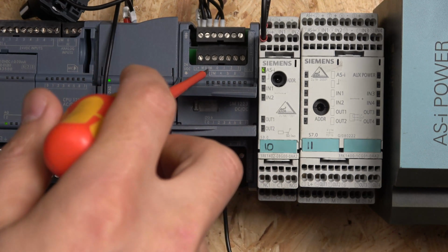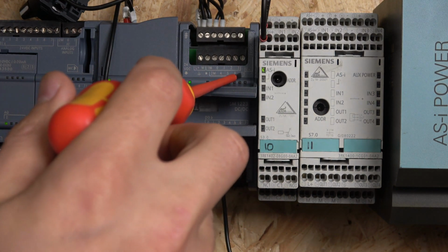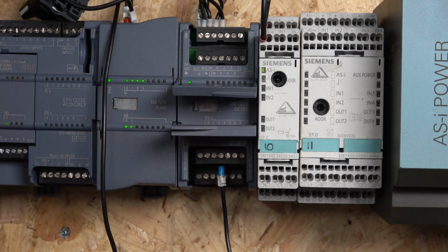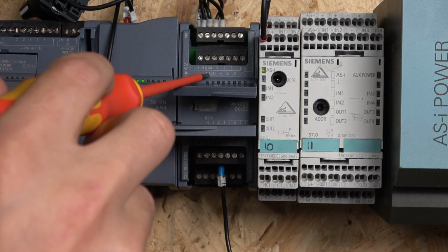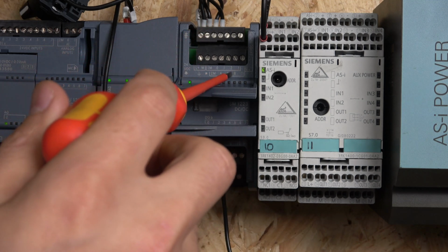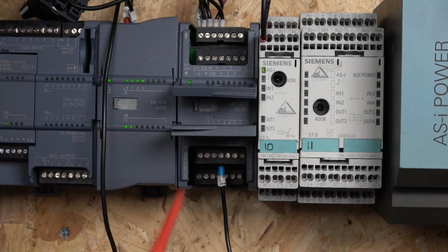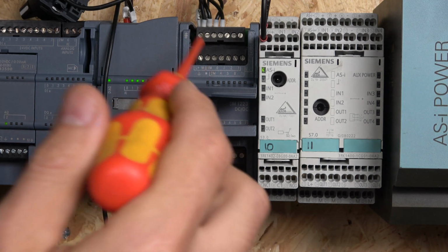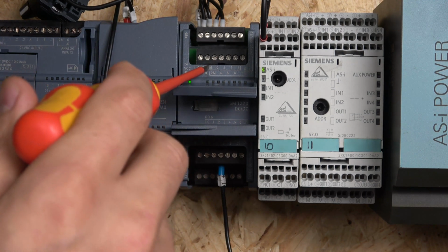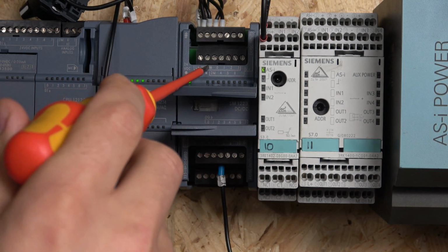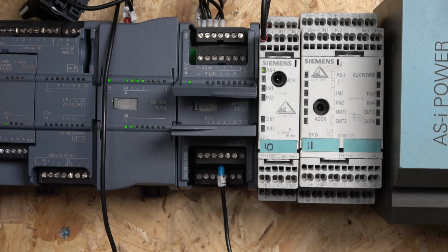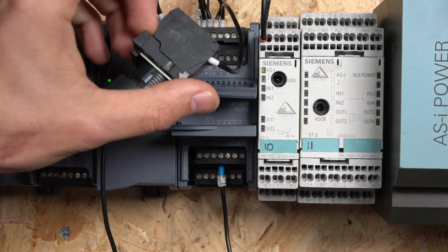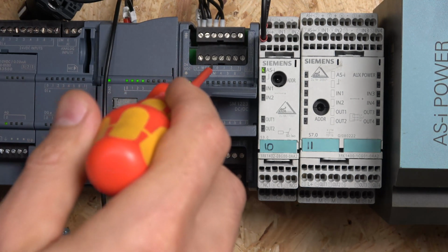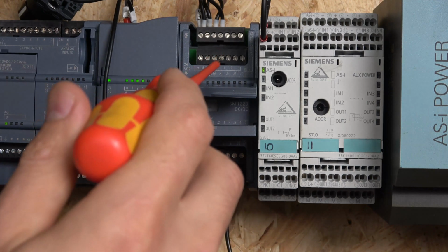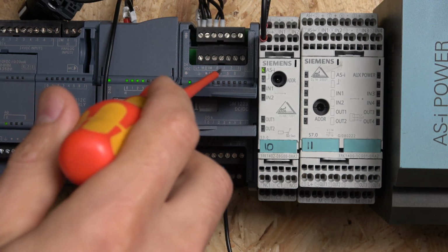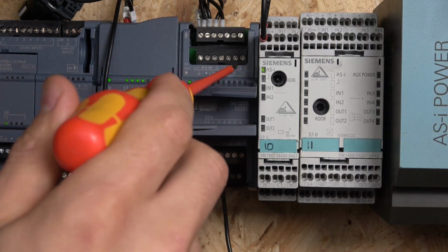As for inputs, as you can see right there, we've got a list of inputs. In total, there are 8, from 0 to 7, and you've got 1M and 2M. Each one of these inputs does require its own negative, and you can send in inputs from a different power supply, as long as the M, which is the negative from whichever power supply you're using, is coming in here, and all the 24 volts you're sending back from sensors or switches is coming from the same power supply. Then it will be able to activate your input. So you are able to have separate power supplies for your inputs if you wish. You could have one for up and one for down.